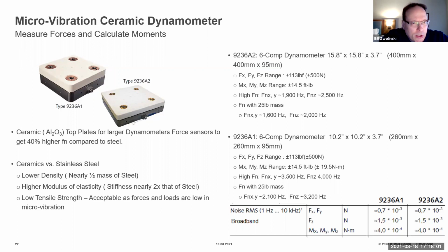Well, to really characterize that, you need a system such as what I'm showing here. It's a force dynamometer, and these could be upwards of say 400 millimeters square, or even bigger. Because they're made with ceramic top plates, and ceramics tend to have a very low density, half the mass of steel, and a high modulus of elasticity, so a higher stiffness than steel, it gives you such capability in terms of measuring low forces.